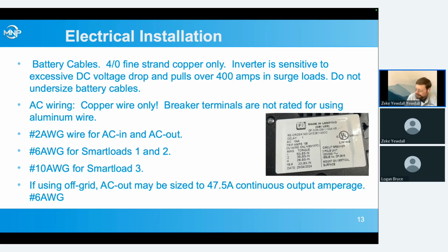We've seen them wired with 2/0 and 1/0 battery cables, and that'll work for lighter loads, but pull a full 20 kilowatt surge off this inverter, which is its rated surge, it's not going to be happy when it's trying to pull over 400 amps off too small battery cables.